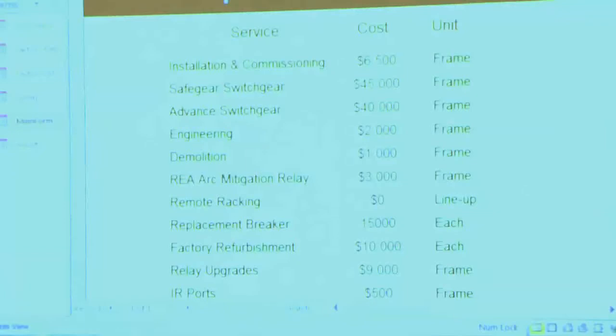And then we've got relay upgrades. Very typically when we quote relay upgrades, like I described before, it's basically removing the door, engineering a new door, mounting a new microprocessor-based relay, pigtailing it over and tying it back in and commissioning it. That runs about $9,000 a frame. And you want to leave that one in?